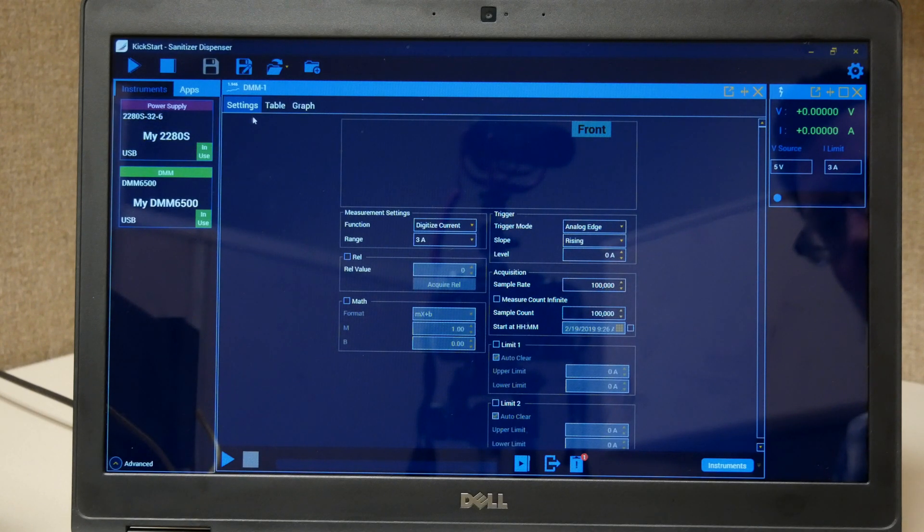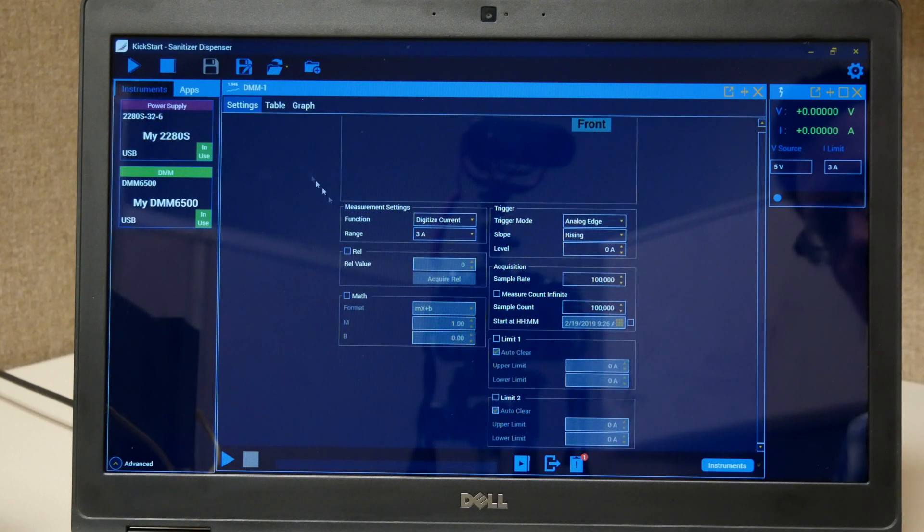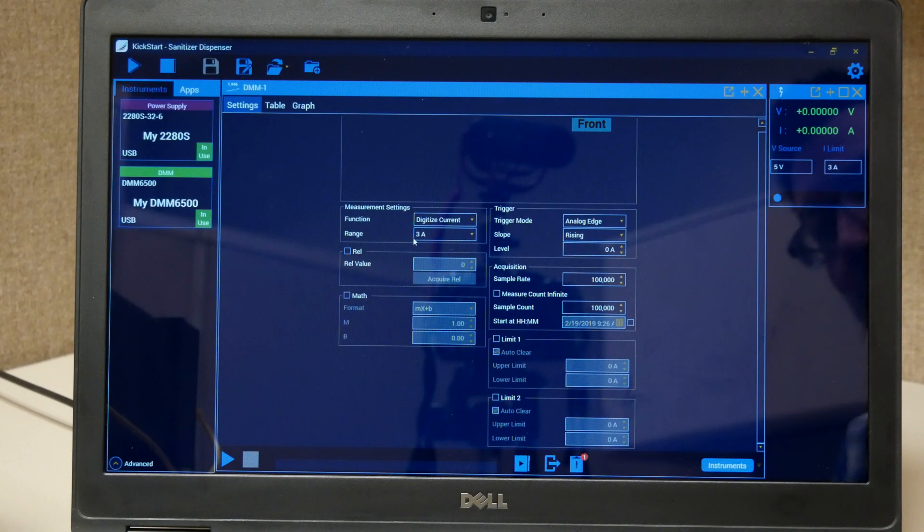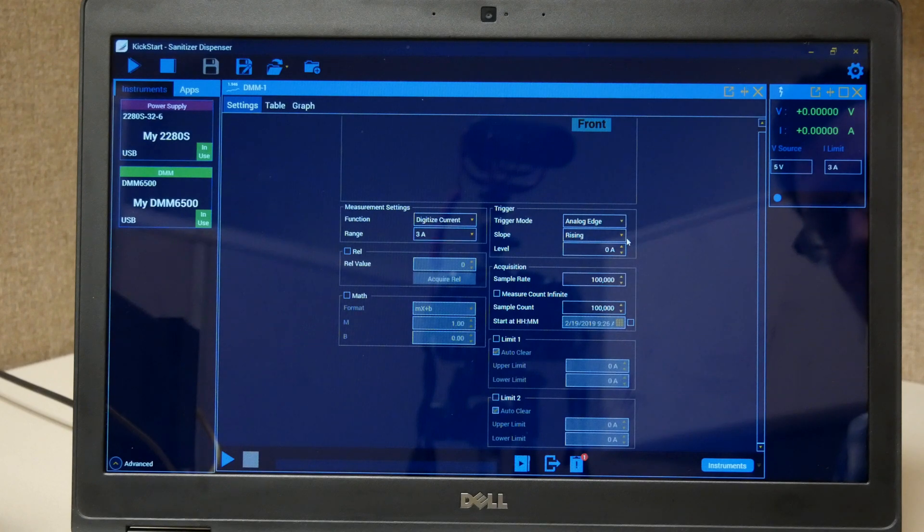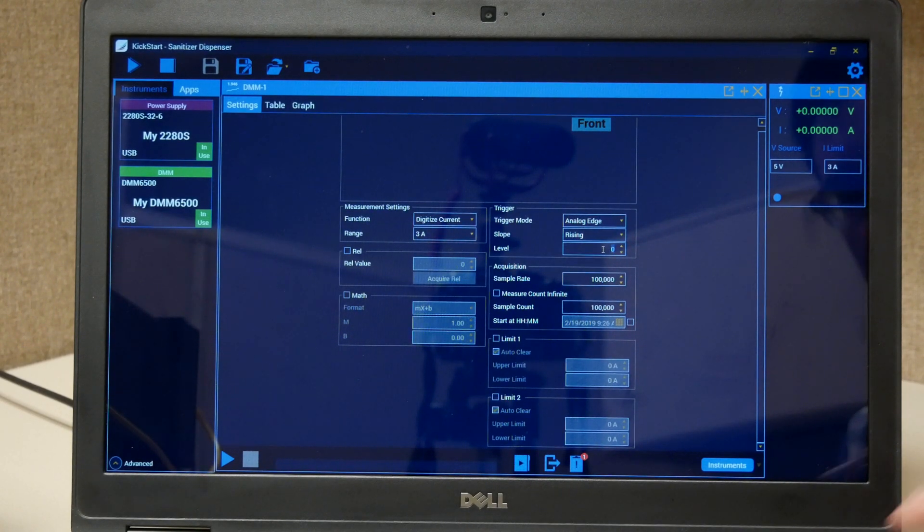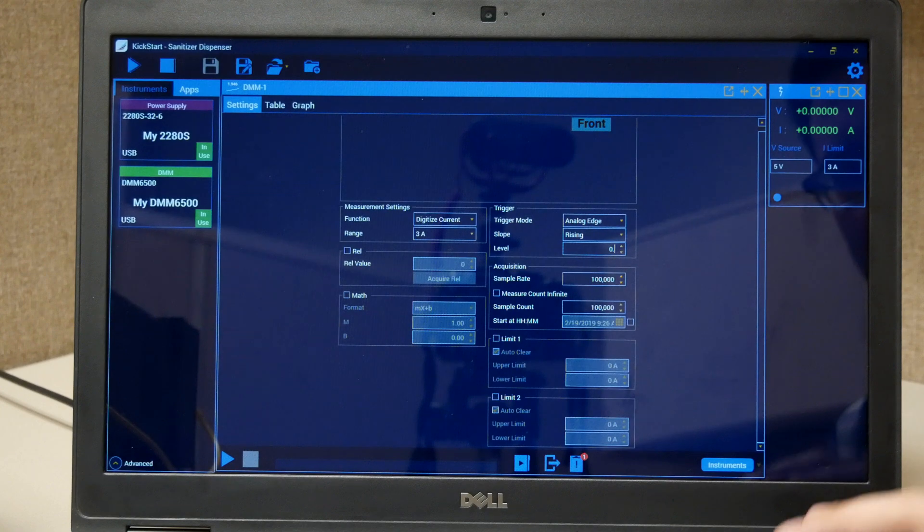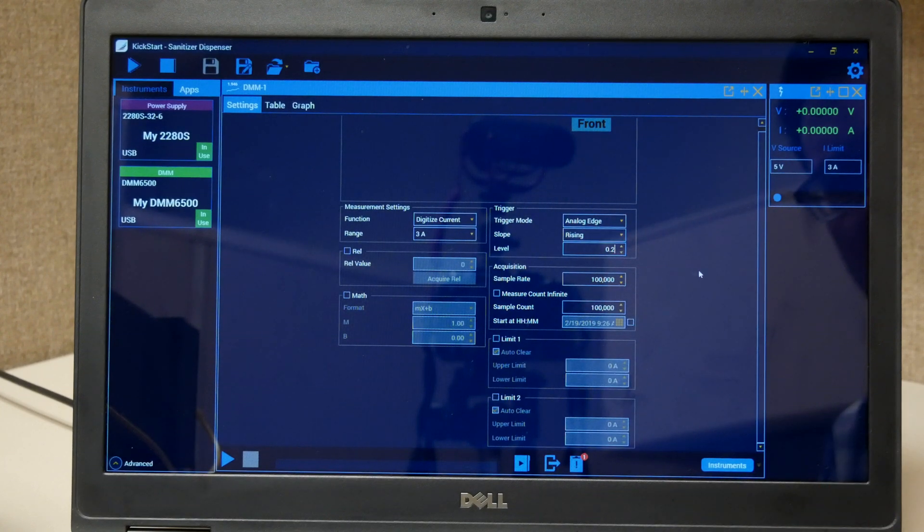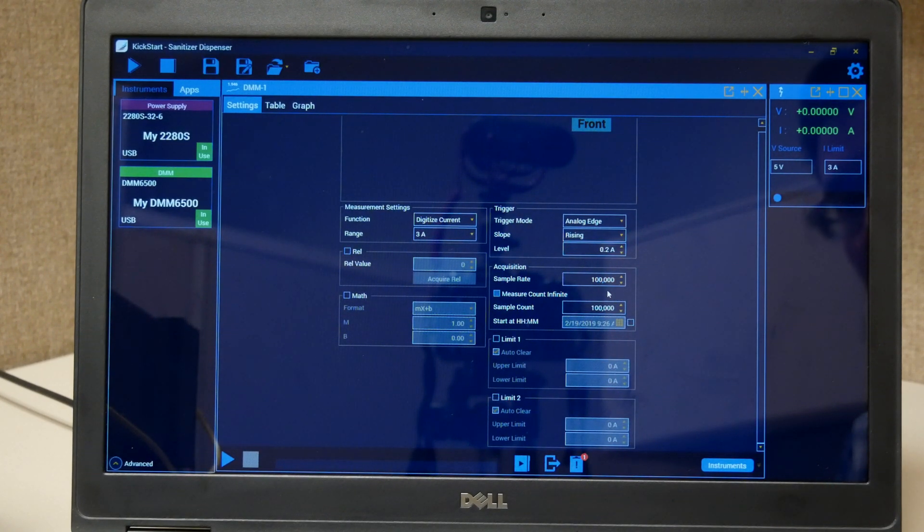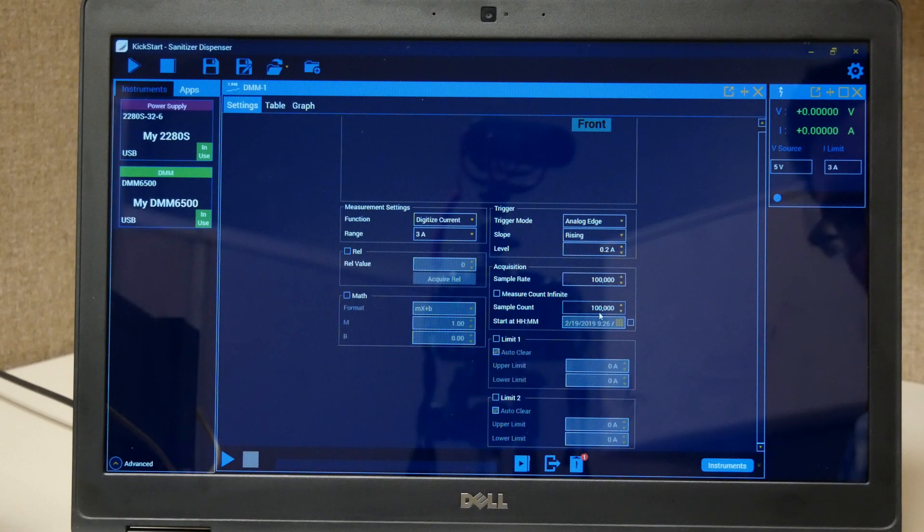Here we can see in the DMM app settings we're set to digitize current with a manual 3 amp range. It's triggering on an analog rising edge and we're going to set this to 0.2 amps. We're taking a sample rate of 100,000 and a count of 100,000.